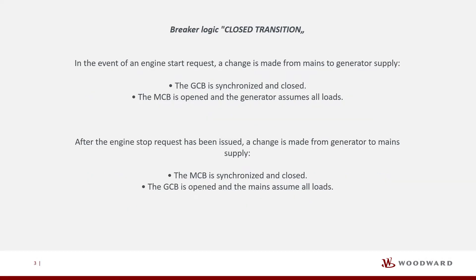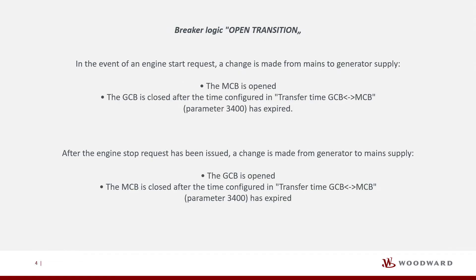Breaker logic closed transition: in the event of an engine start request, a change is made from mains to generator supply. The GCB is synchronized and closed. The MCB is opened and the generator assumes all loads. After the engine stop request has been issued, a change is made from generator to mains supply. The MCB is synchronized and closed. The GCB is opened and the mains assume all loads.